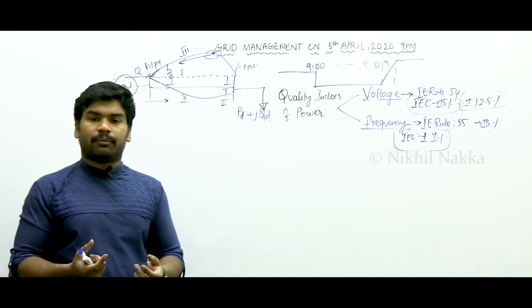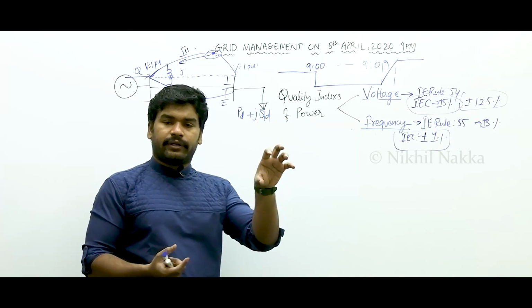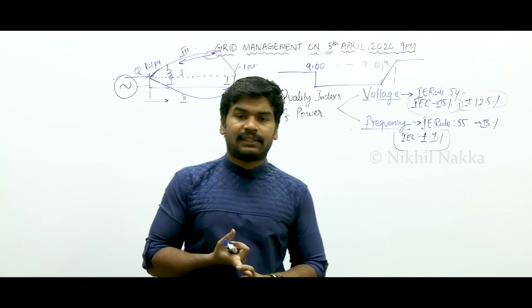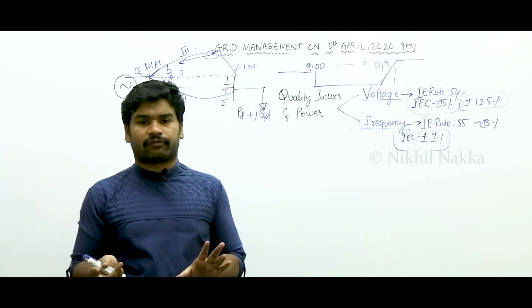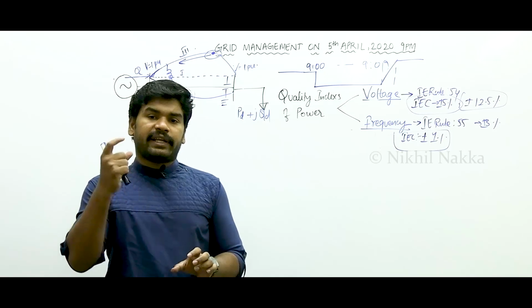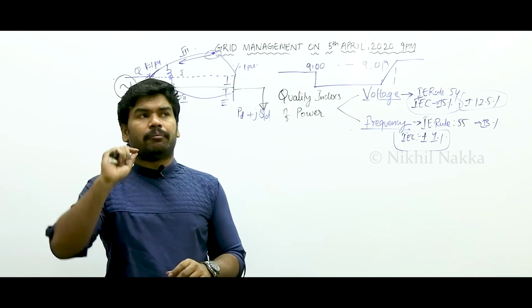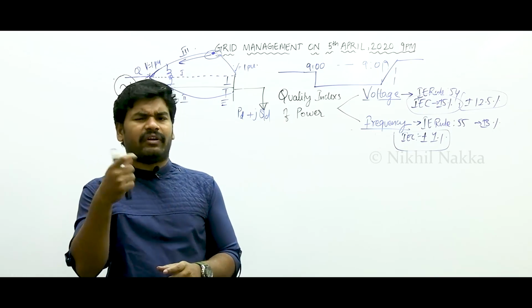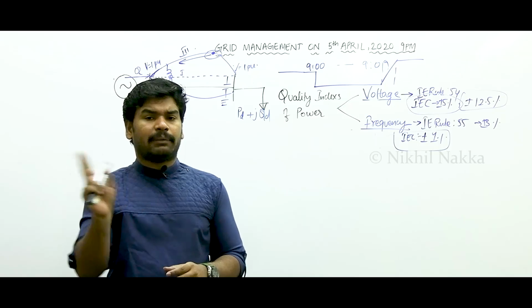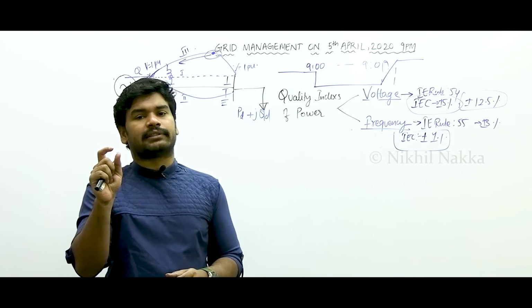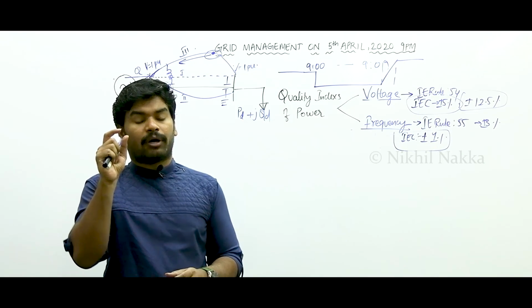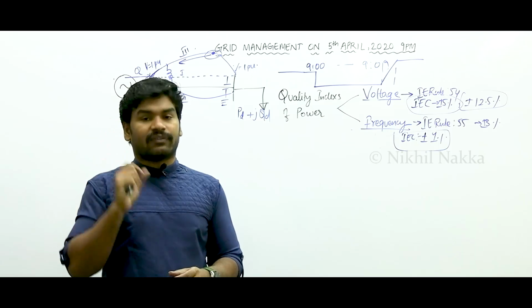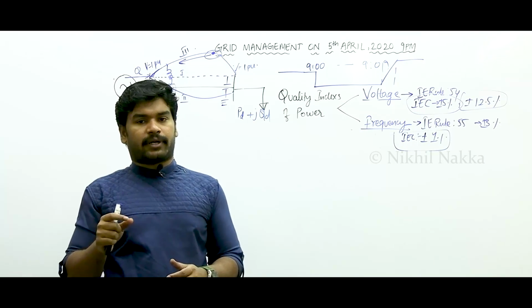Why do they require reactive power? Because they have that choke, isn't it? That choke requires reactive power. Like that, reactive power demand is still there, it is not gone off. Of course, the reactive power change due to switching off of lights and all will be very less. Here the problem is not about the magnitude, guys - here the problem is with rate of change of load, rate of change of reactive power.